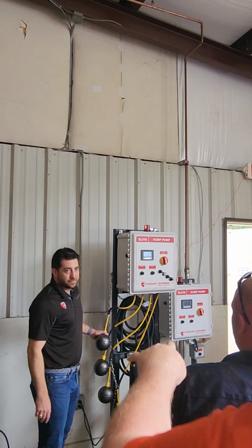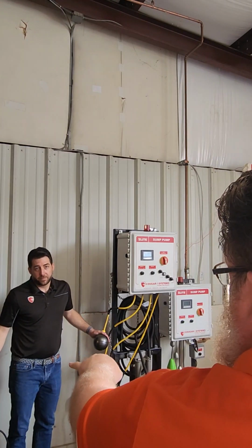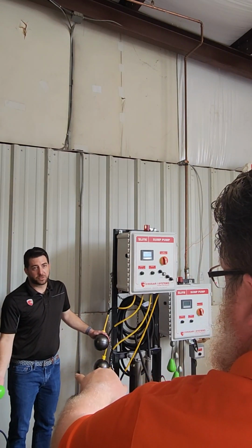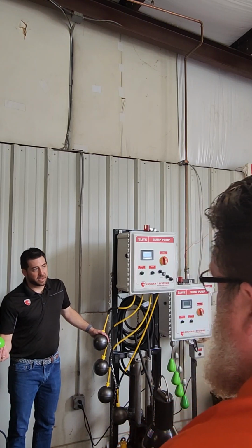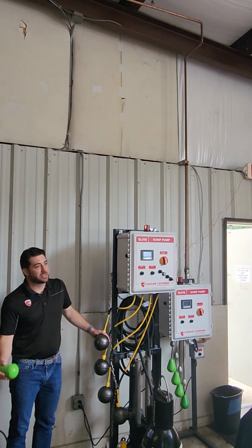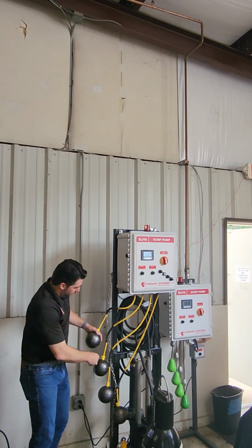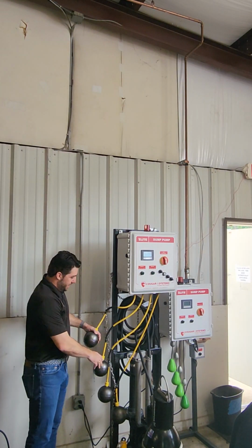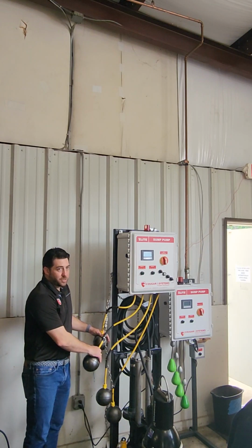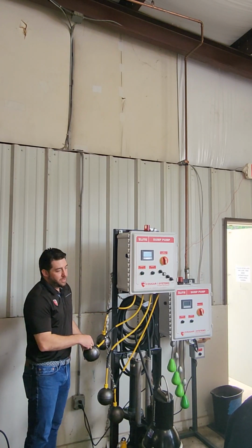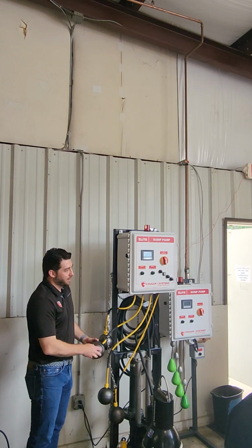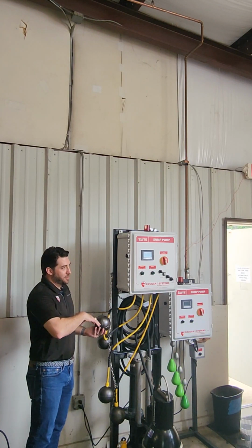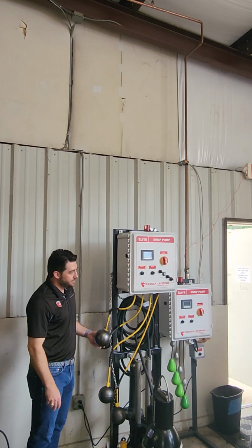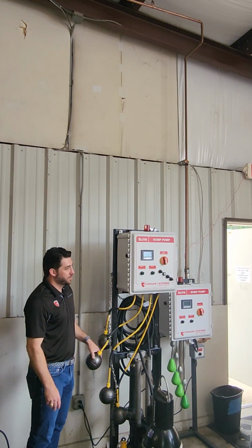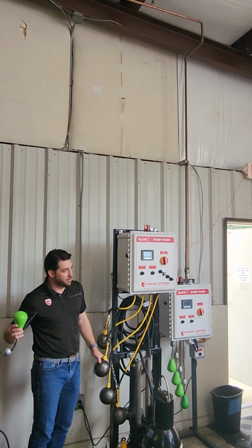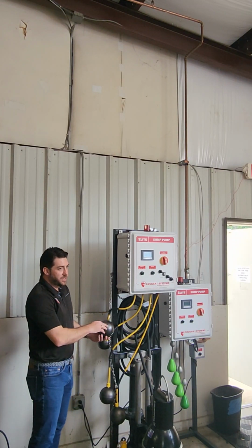So what'd you say the difference between that one and that one is? The price, or what's the difference? So these are plastic and these are a mechanical float switch. Inside there is a ball and contacts, and when it flips up, that ball connects the two contacts, and that's how you're making your float switch. These are stainless steel, Teflon coated, they're sealed, and it's still a mercury switch. Like liquid mercury? Yeah. When the mercury slides over, it makes the contact. You don't even feel that one activated. There's nothing inside there that you feel, like from this one, you can feel the ball or hear the ball. There are mechanical versions of these, but we typically get the mercury.